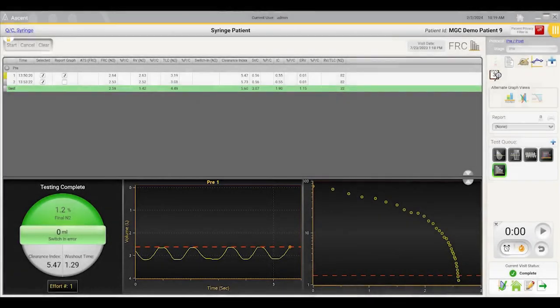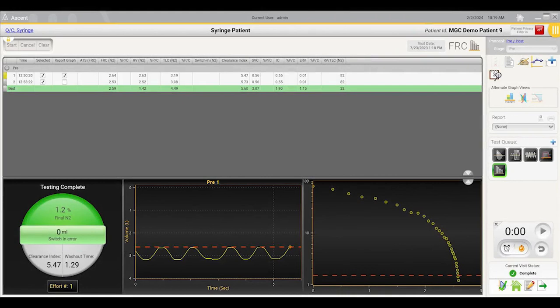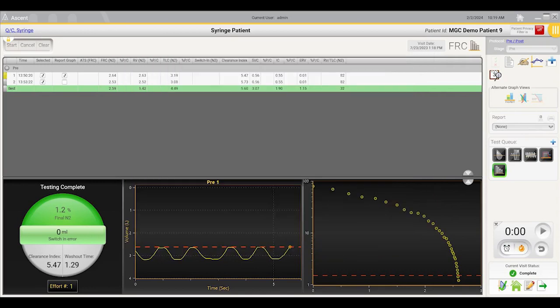Proceed to the N2 washout test screen. Before each N2 washout effort, place the umbilical clip into the calibration port and perform a gas calibration.